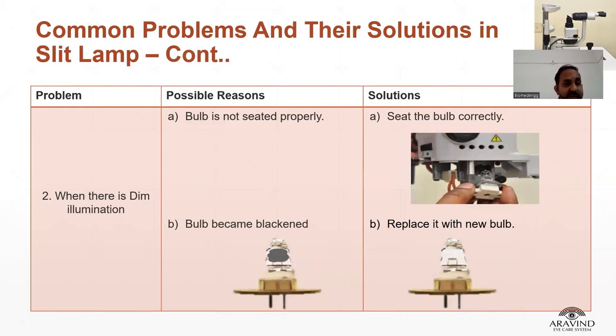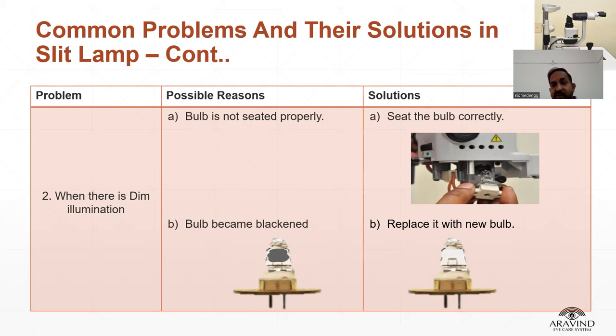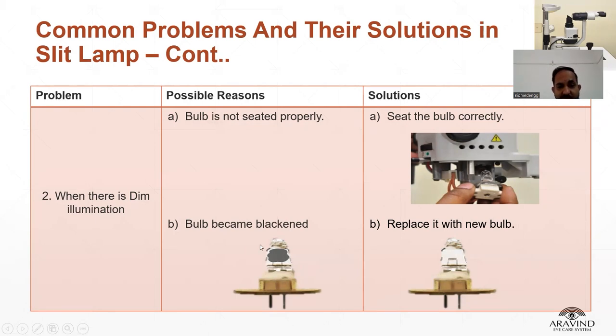The second problem is dim illumination. The possible reason is that the bulb is not seated properly in the bulb socket, which prevents proper light output and results in an unclear image. Check and reseat the bulb in the socket. Sometimes the bulb becomes blackened, in which case it cannot be repaired and must be replaced with a new bulb.